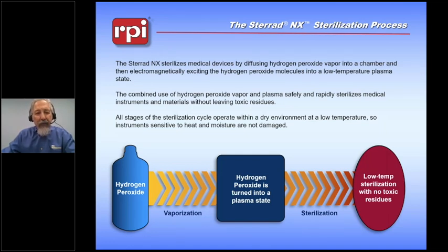It uses a solution of hydrogen peroxide to sterilize the material within the chamber. This hydrogen peroxide is delivered as a 59% solution. It's concentrated down to 90%. Then it's injected into the chamber with all the material, and then it's turned into a plasma. And the plasma will take the 90% hydrogen peroxide, turn it into water and free radical oxygen, which will actually do the sterilization process.